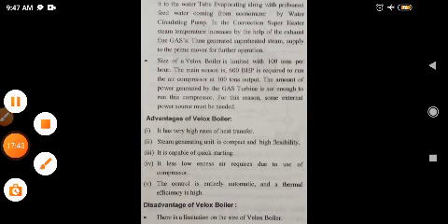But can you remember the things that we have seen up to this lecture? That is the Lamont boiler. In the Lamont boiler, there is forced circulation. It was a forced circulation boiler, forcing high pressure water through the tubes. This is generally used in Europe and America. The feed water from the hot well is supplied to the steam and superheating drum through the economizer. Most of the sensible heat is supplied to the feed water passing through the economizer.